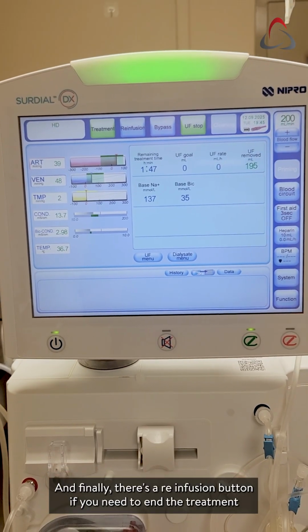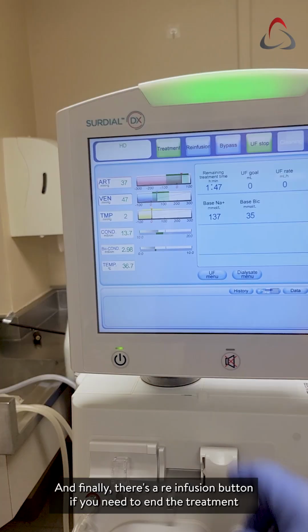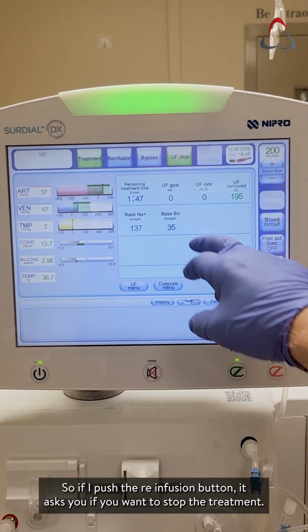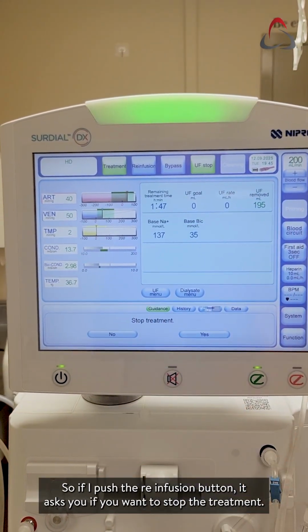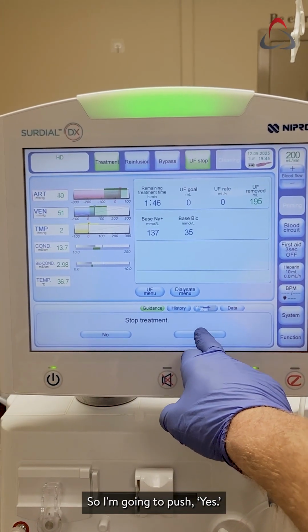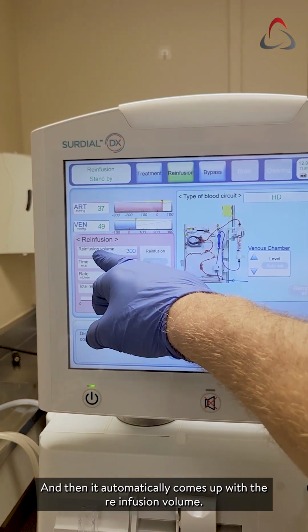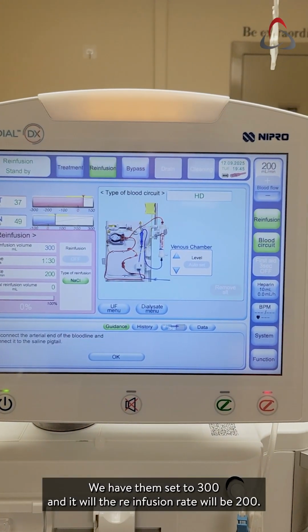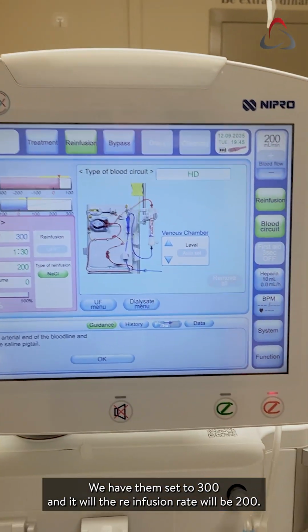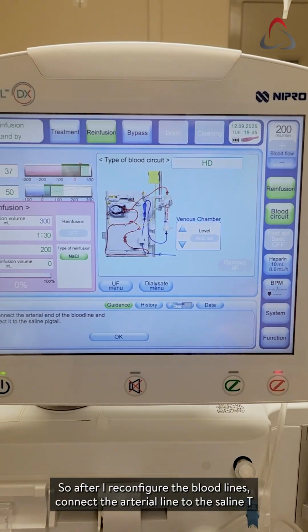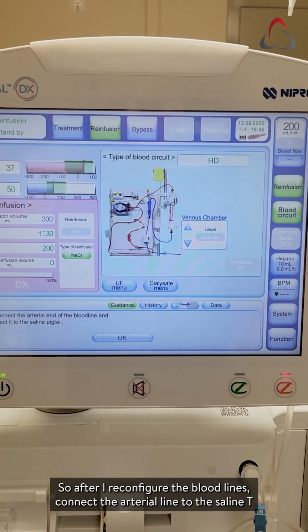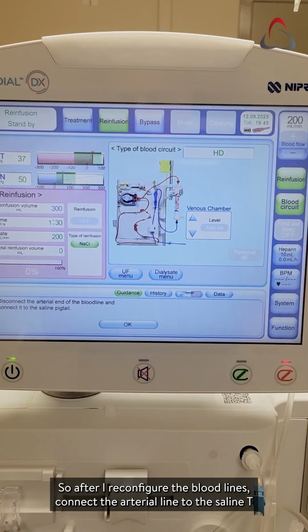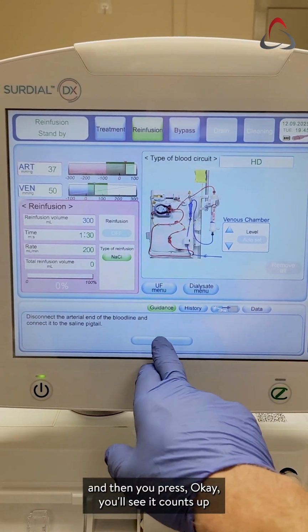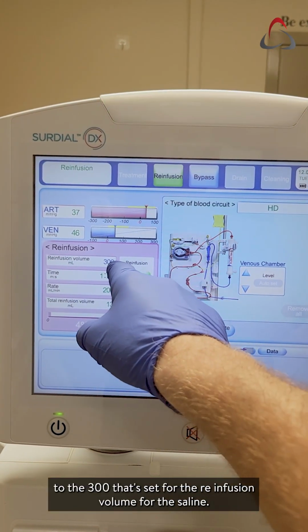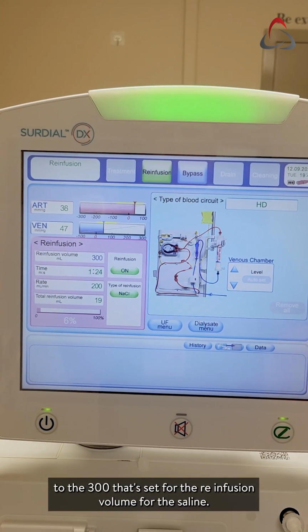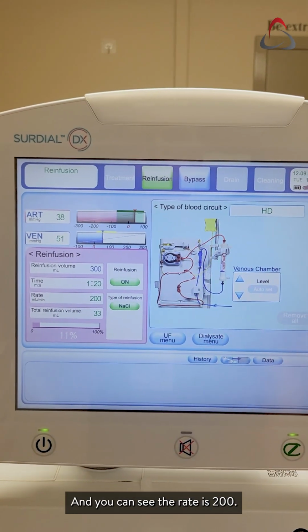And finally, there's a reinfusion button if you need to end the treatment early for whatever reason. If I push the reinfusion button, it asks if you want to stop the treatment. I'm going to push yes. Then it automatically comes up with the reinfusion volume. We have them set to 300 and the reinfusion rate will be 200. After I reconfigure the blood lines, connect the arterial line to the saline T, and press OK, you'll see it count up to the 300 set for the reinfusion volume for the saline, and you can see the rate is 200.